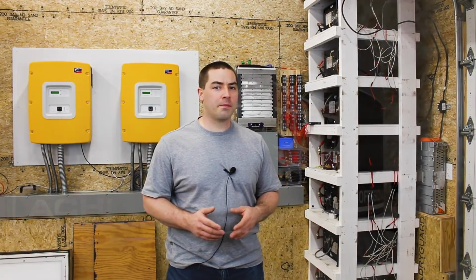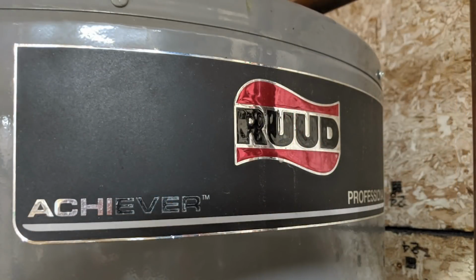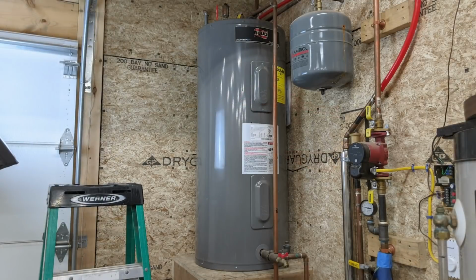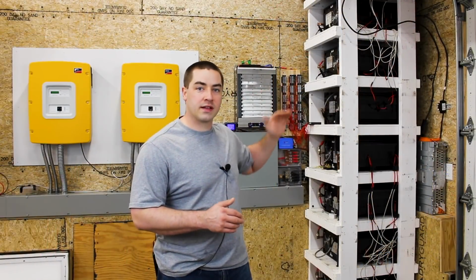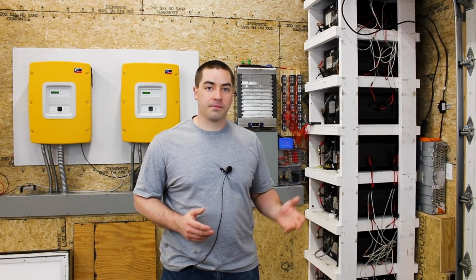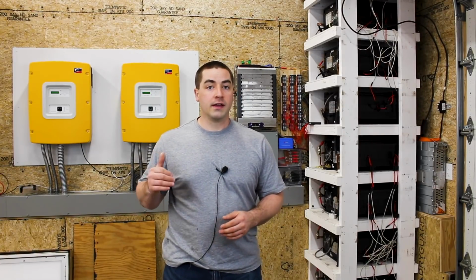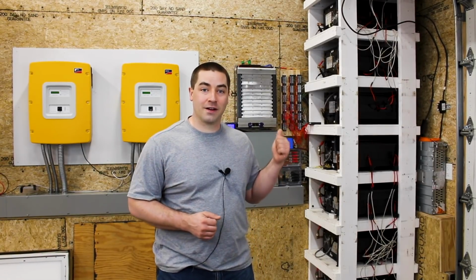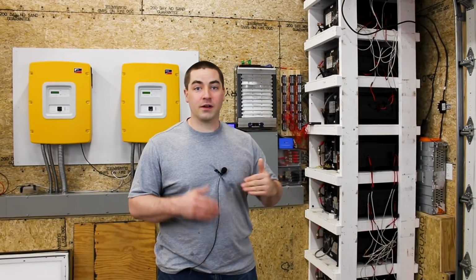Today, we're going to wire up a water heater as a load. This will serve two functions for us. We're going to do a capacity test, but not just what 100% to minimum is, we're going to find out what the usable capacity is as it sits. The second purpose is to wire it up to a relay controlled based on state of charge, so when the batteries get full, it will divert the excess power to that load.